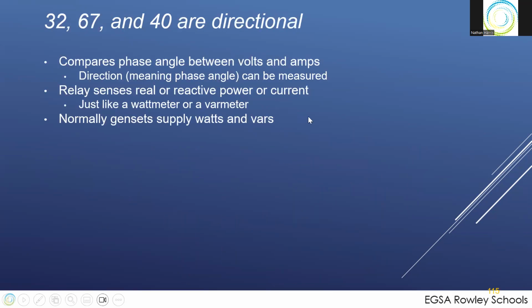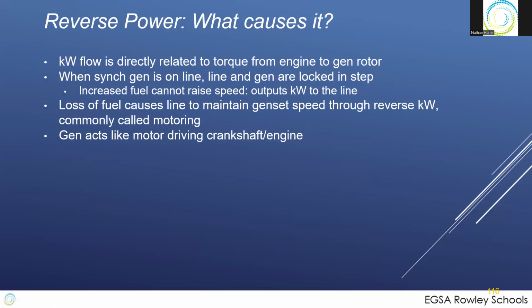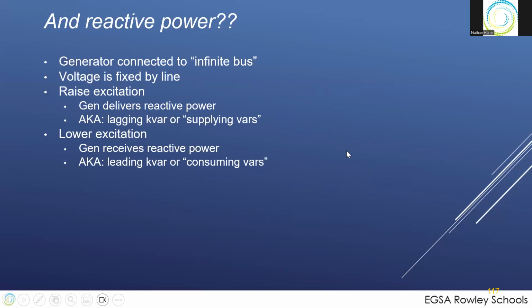And we have differential relaying, and it looks at power in and power out. Reverse power, which is not differential, is power flowing back into the engine and driving the motor, the crankshaft. And then reactive power is consuming VARs off a system.